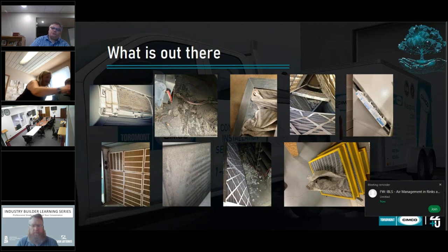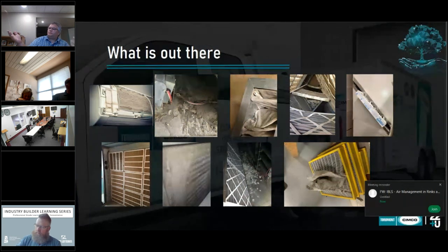I've got a picture that shows pleat direction - there's a right way and a wrong way. Invariably, I see coils become filters. People just say it's getting dirty, and then all of a sudden the system seems to be running better, the gauges have dropped, and nobody bothers to inspect - you see a filter that's completely and totally blown out.